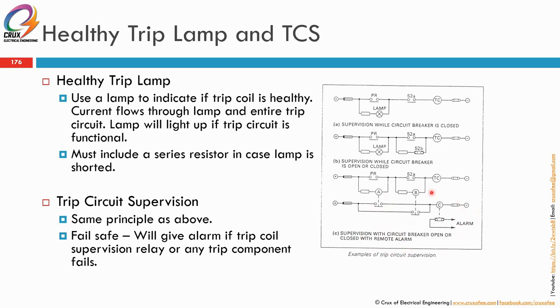And this is the trip circuit supervision. Same principle as above. Instead of the lamp, the lamp is replaced by a trip circuit supervision relay. So if there's any problem, it will trigger the contact and give an alarm. This alarm, you can trigger a buzzer or send to a binary input of your protection relay to indicate you have a trip circuit supervision issue, meaning there's a break in your trip circuit.